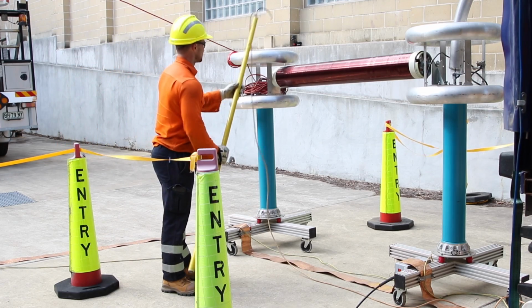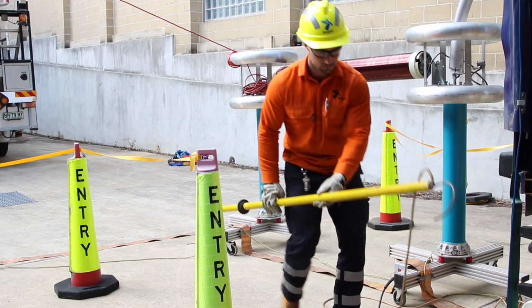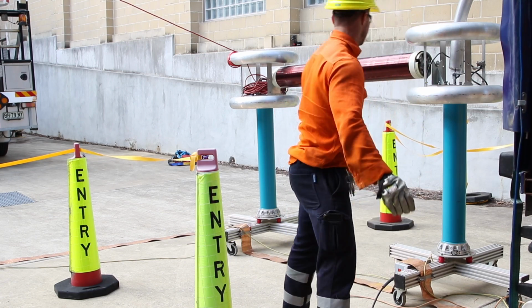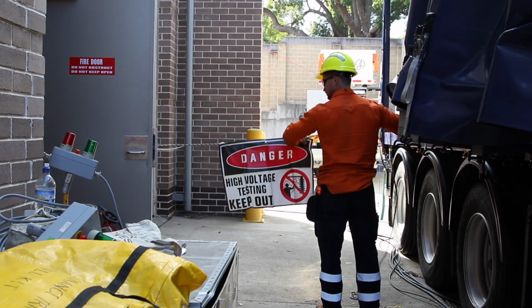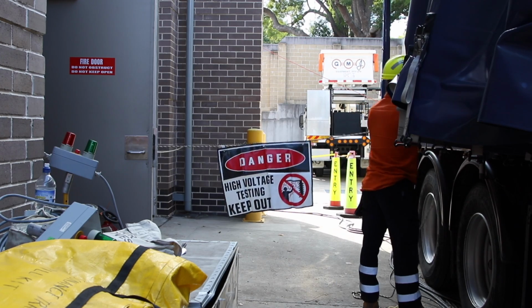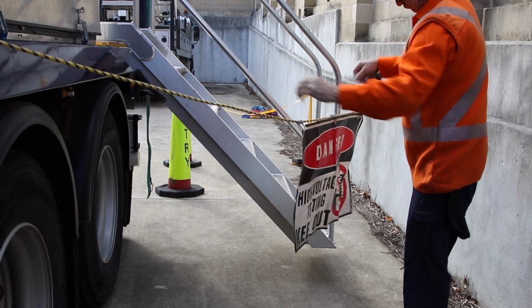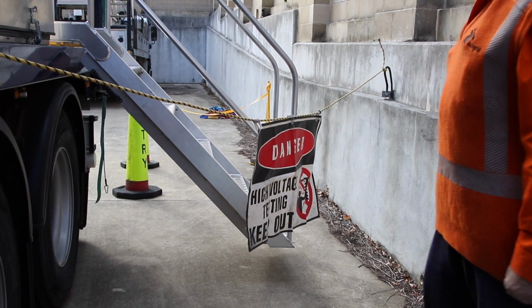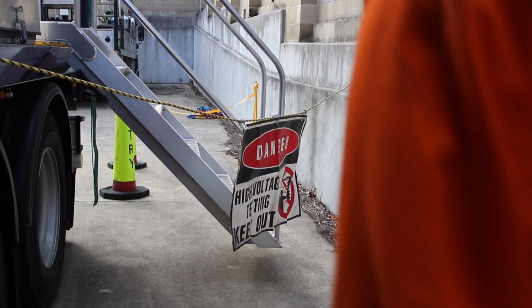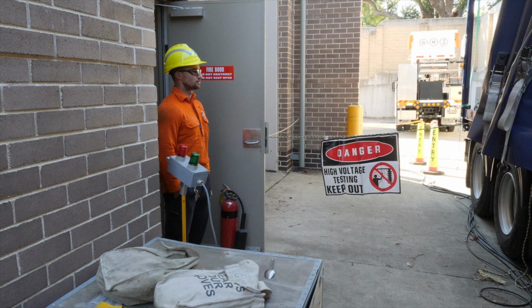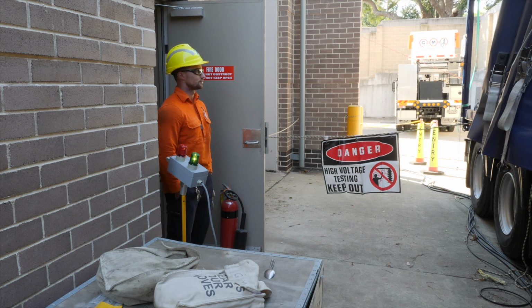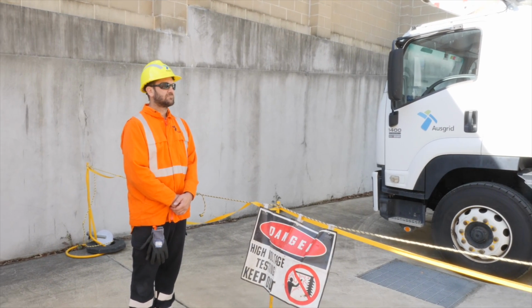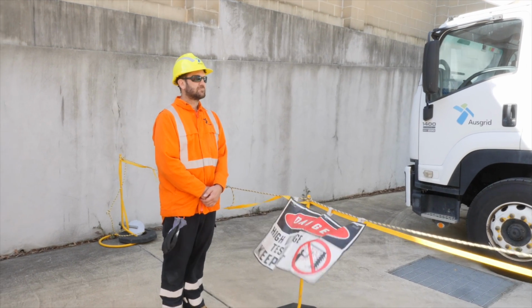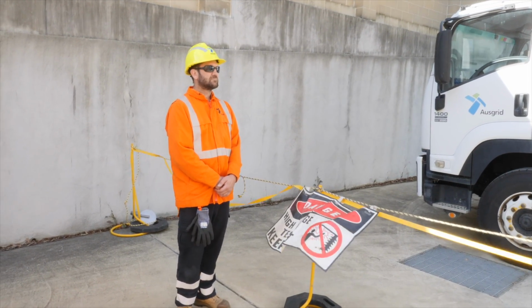The manual earth will now be removed from the test trailer output to make the test circuit ready for high voltage. The exclusion zone around the test trailer, voltage divider, high voltage line and test object are designated by black and yellow rope and danger signs to prevent access to the hazardous voltages used for testing. Observers are positioned in locations to monitor access to the area and warn anyone approaching the area of the dangers present and to prevent unintentional breaches. The test area is now deemed active and ready for high voltage.